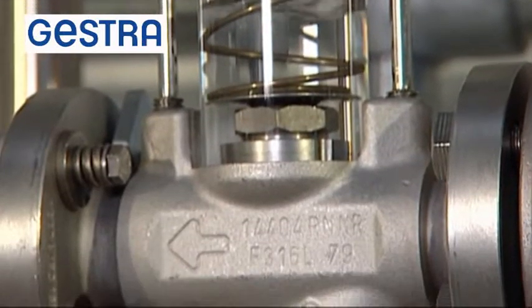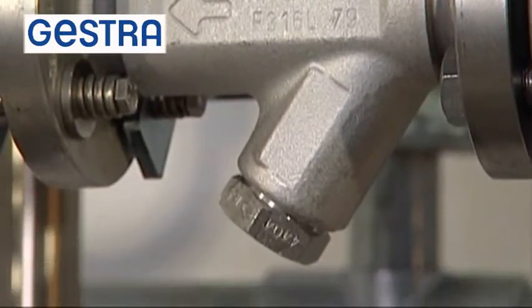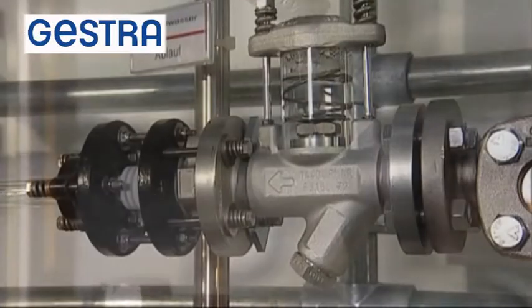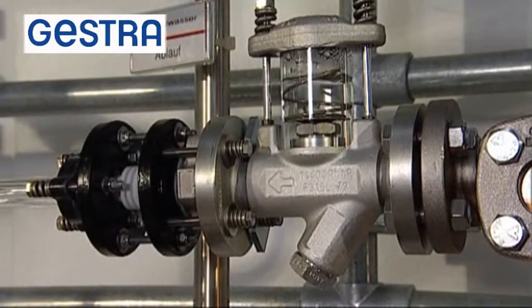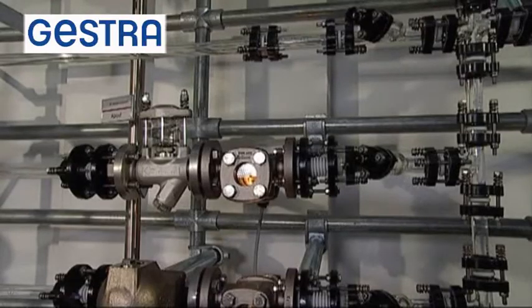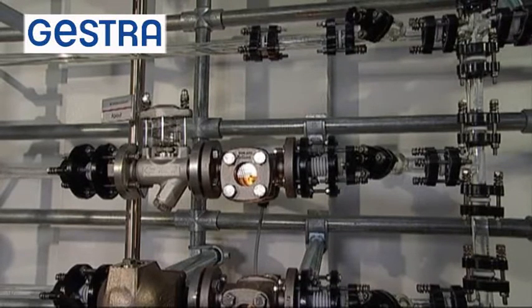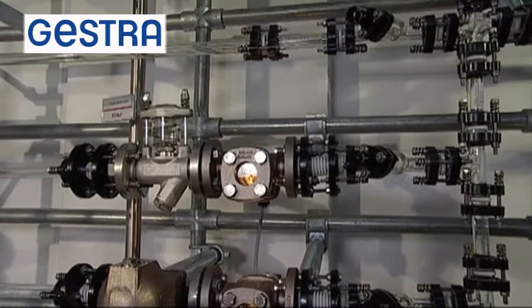Even for controlled plants, in which the steam pressure fluctuates, this has hardly any influence on the condensate discharge, which is usually achieved without banking up, provided the steam trap is sized correctly. The back pressure has no influence on the control accuracy. Let us first consider the functional principle of the steam trap installed in the horizontal pipe.